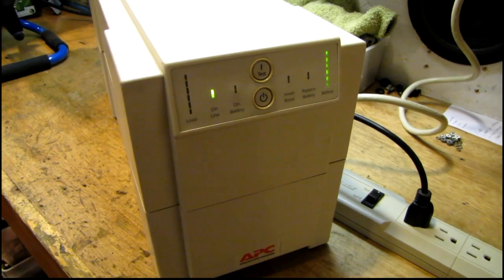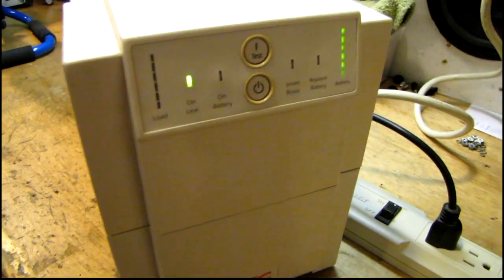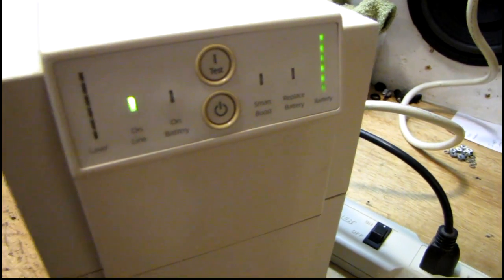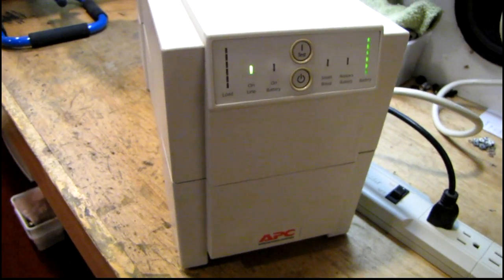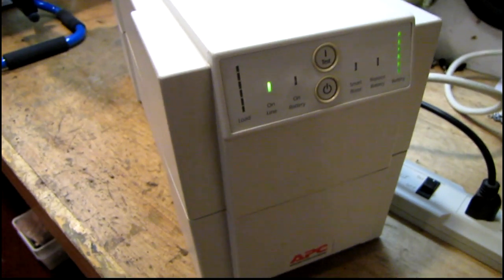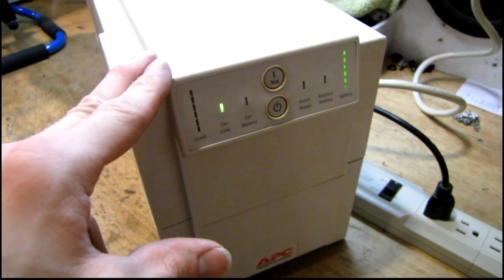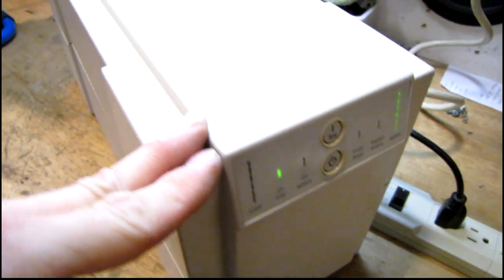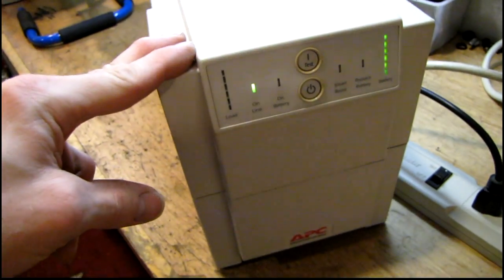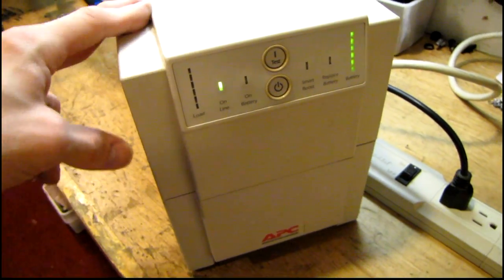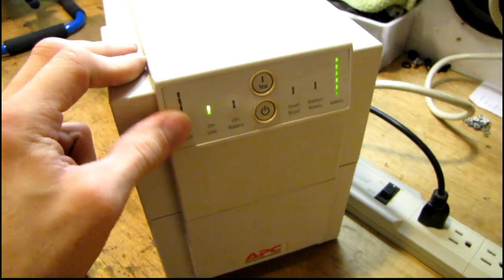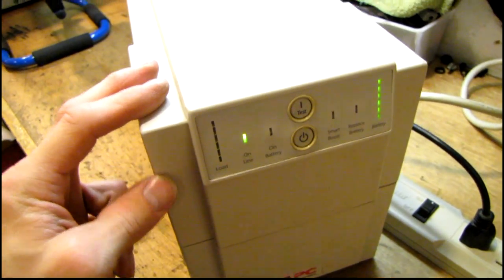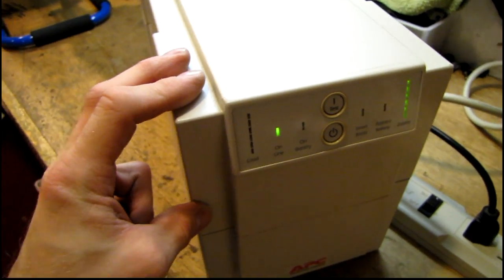Okay, now the batteries are fully charged. The gauge is reading all the way up and the cooling fan is not running. That means the unit is sitting idle and you can start your calibration. What you need to calibrate the batteries on these accurately is something that will put a purely resistive load that does not change.